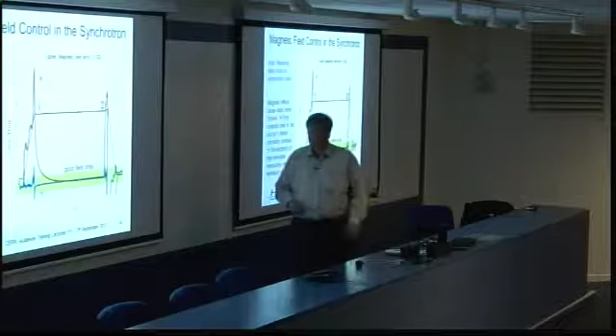So this is a normal situation. You have your central control system, you have a power supply for the dipoles in the synchrotron. You put a set value to that power supply, and that leads to a current in the magnet. Okay, the current is controlled by the DCCT, and then it's regulated. So this is a normal system we had before. Now we added a Hall probe here for a starting value at the injection level for the magnetic field, and we had a pickup coil that we integrate these signals from in our B-integrator, as we call it. This is a delicate piece of electronics. I can show you only the front plate.